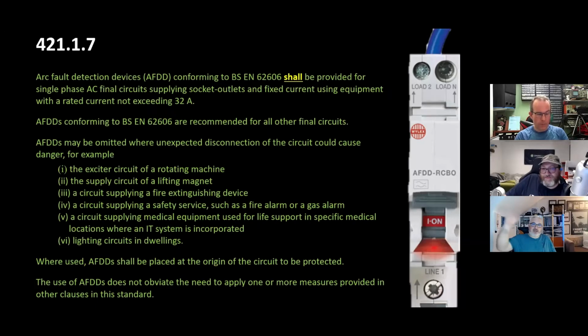This is the problem where energy efficiency has impacted the AFDD market quite a bit, because they need a minimum level of energy to see that arc and understand that it's a serious fault. That's what we're not talking about enough. But we'll cover a bit on RCDs too. I don't disagree, they are a good thing, even if we're having the can kicked over our fence by the white goods industry. We just need to get good at selecting and erecting these, which means a lot of thought.